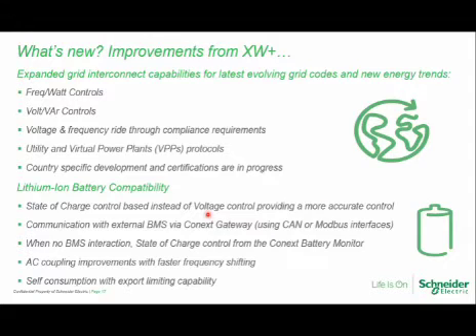This basically covers the advantages the XW Pro has over the XW and the XW Plus. For lithium-ion battery compatibility, you can use state of charge instead of voltage for controlling your system or measuring output power to your loads, with communication through the BMS of the battery, like a PYLONTECH battery, which you'll see in the closed loop compatibility. When there's no BMS with the lithium-ion battery, you can use our battery monitor to perform state of charge control, which you previously could not do.